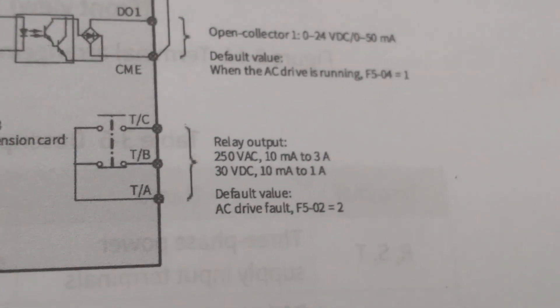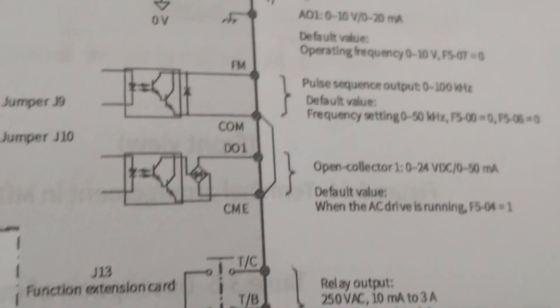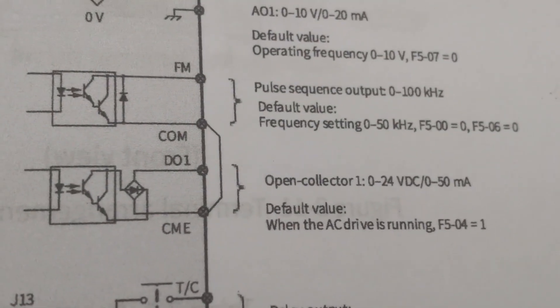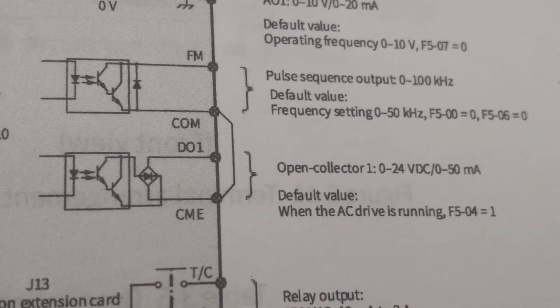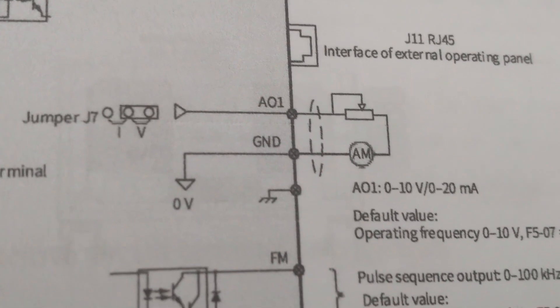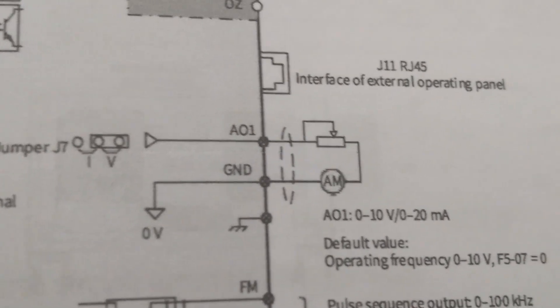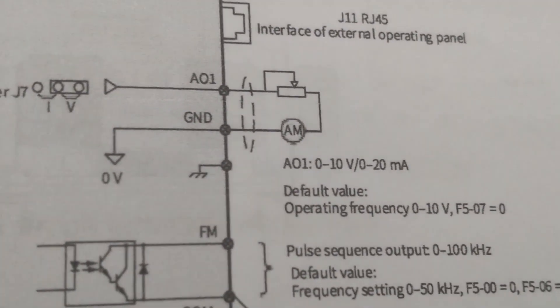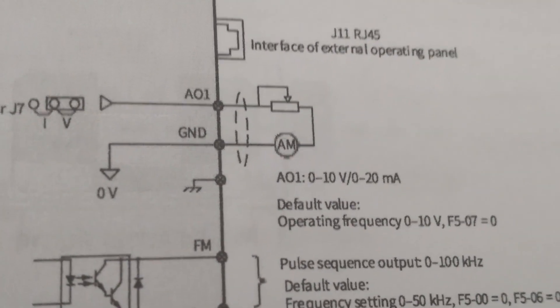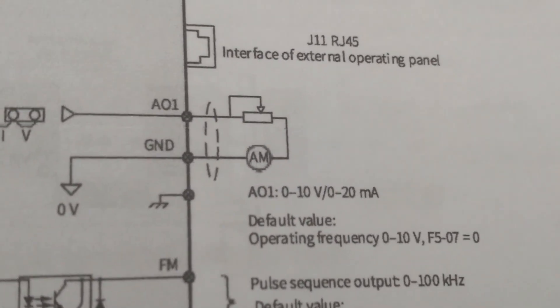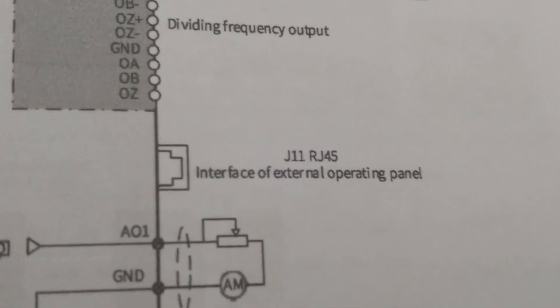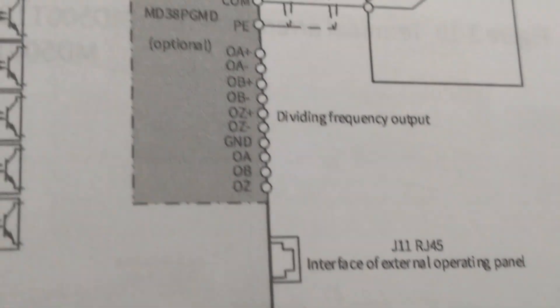Remember that by default, relay is programmed to activate on fault condition. DO1 is digital output terminal. FM terminal is used to generate pulse signal. AO1 is analog output terminal. It generates 0 to 10 volt or 4 to 20 milliampere. RJ port is provided to connect external operator terminal.